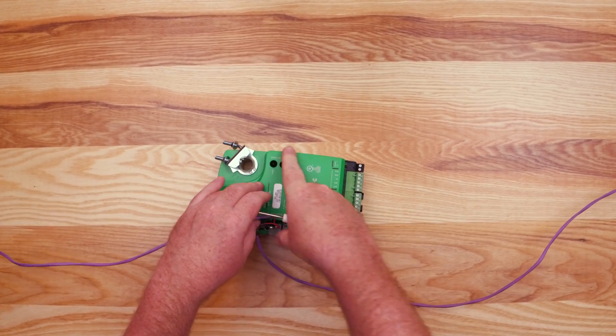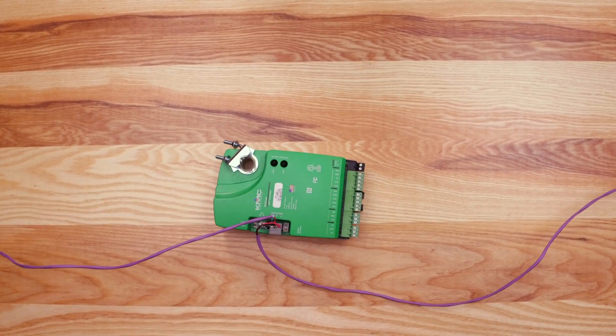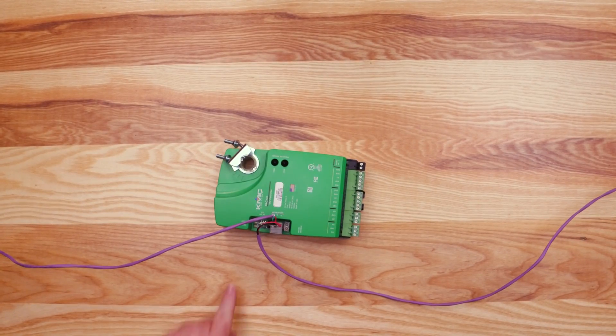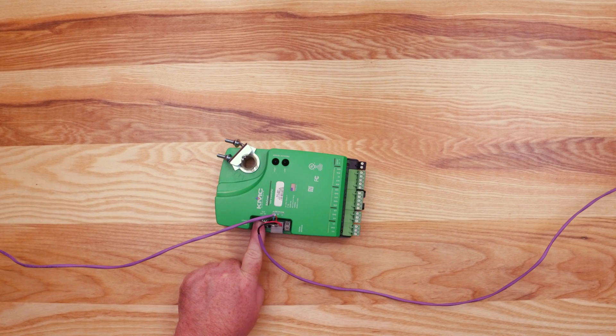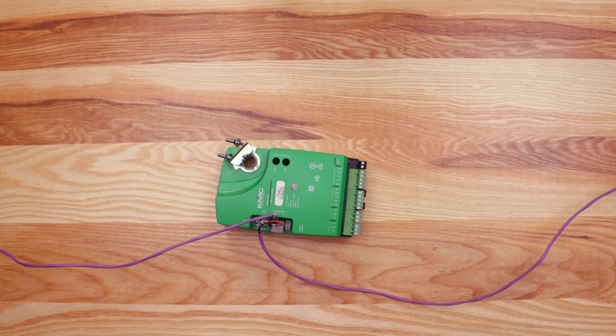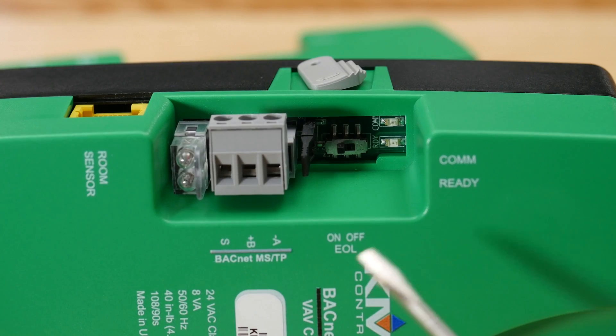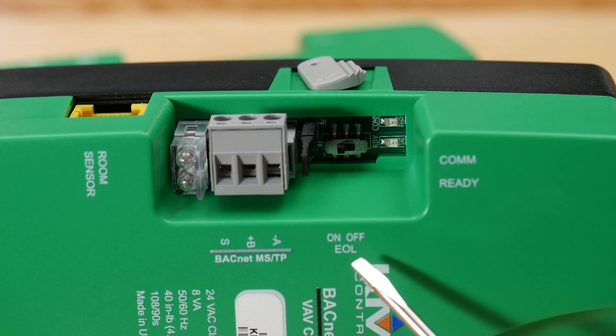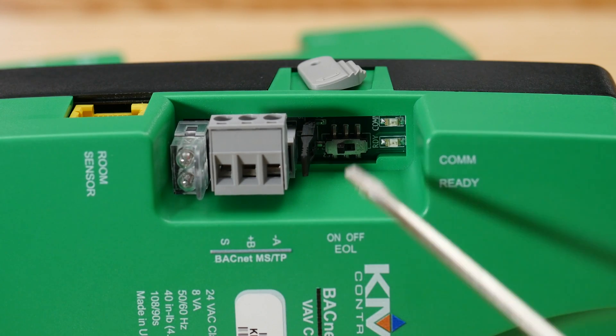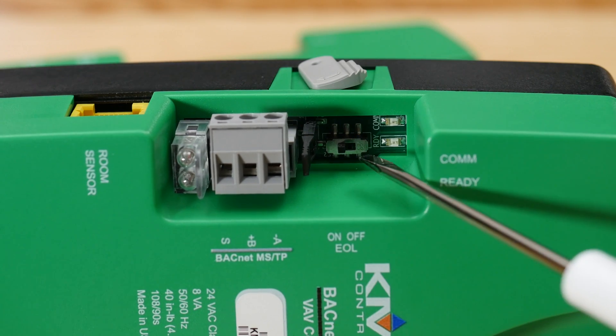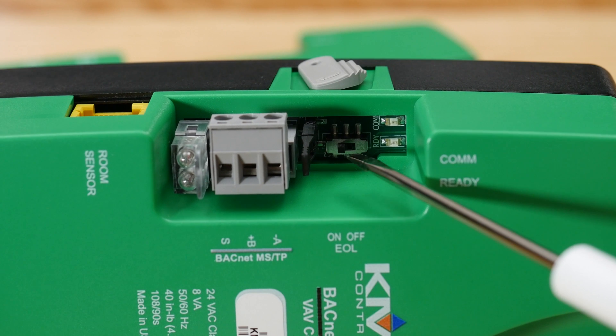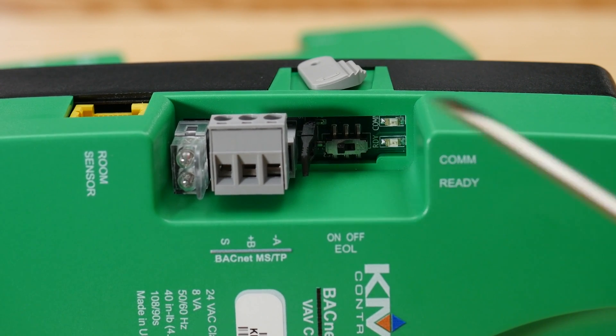At one end of the network, it is important to connect the cable shield to a good earth ground to avoid network interference. If the controller is at either end of a BACnet MSTP network, turn the EOL or end of line switch to the on position. Your controller is now connected to the MSTP network.